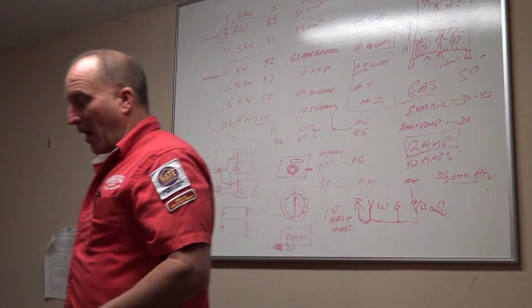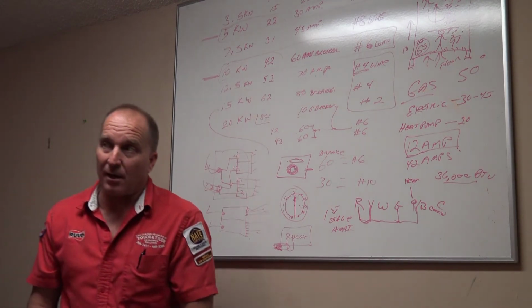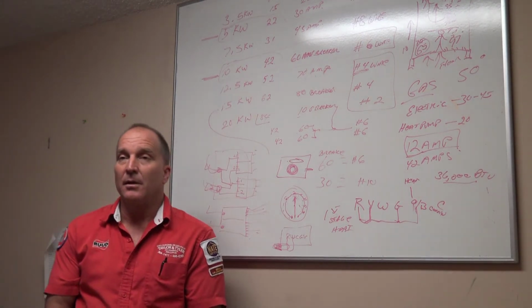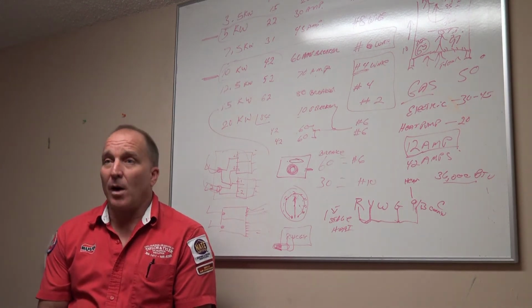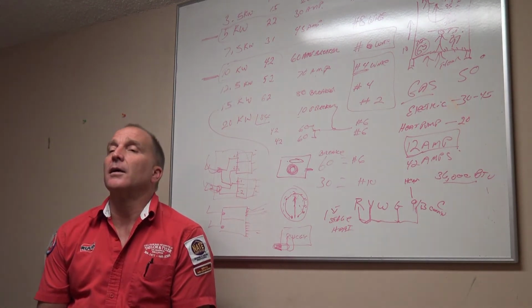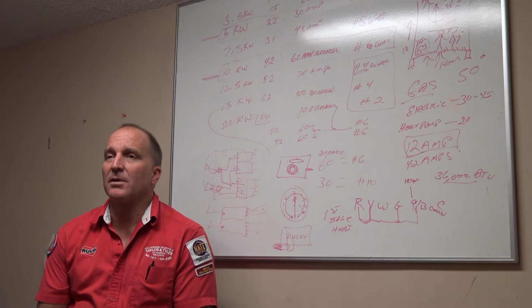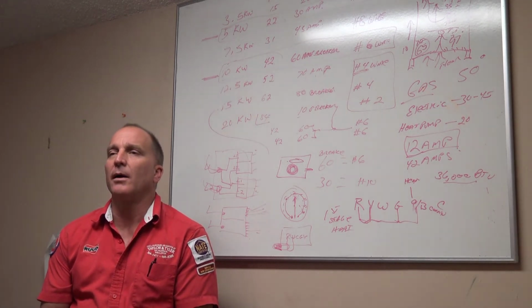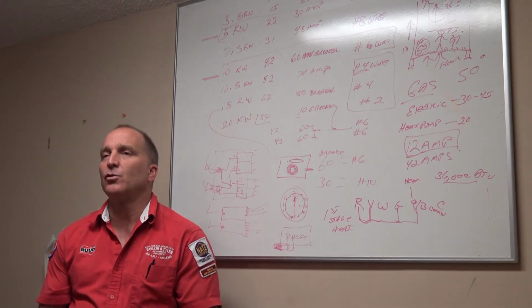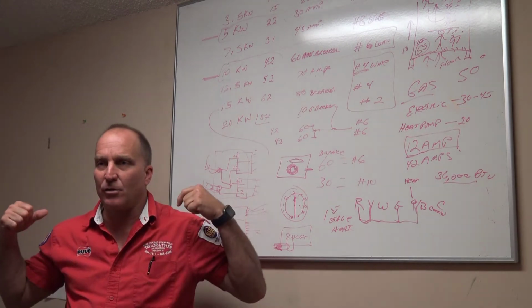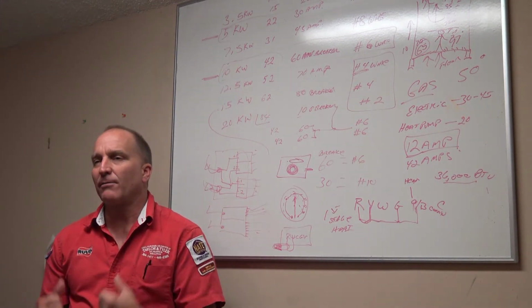But guys, your wire sizes, I can't stress enough. If you're checking an electric heat system, wire size, wire size, wire size, breaker sizes, fuse sizes, how many amps are you drawing? Are you drawing too many amps? Did you check all your electrical connections? Did you check for heating? Did you check for burning of it?